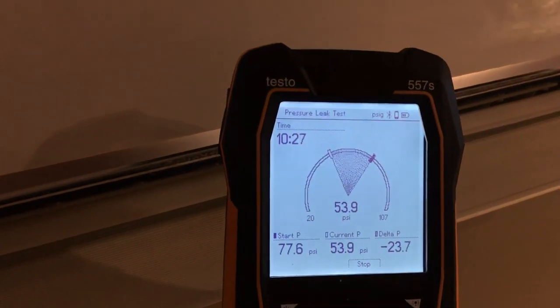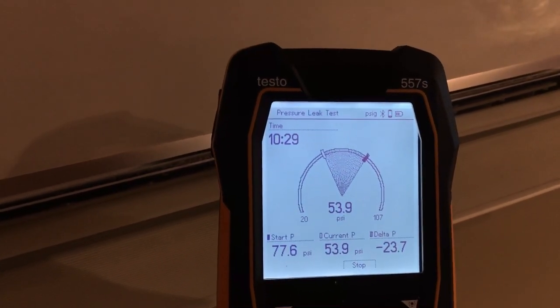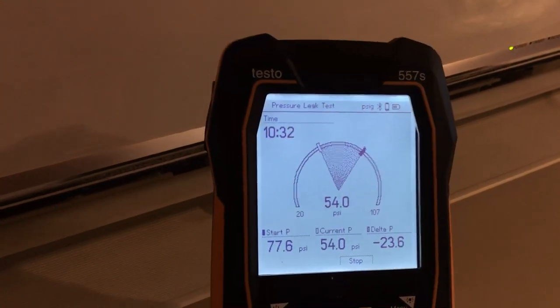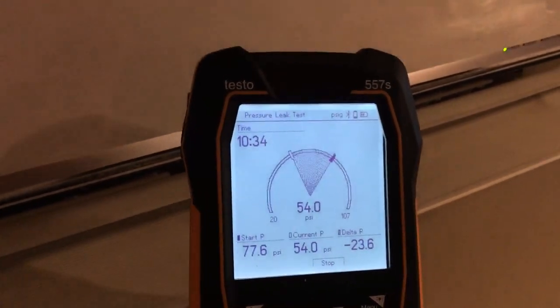So do not try to do pressure tests, standing duration pressure tests, with any kind of refrigerant. Dry nitrogen only. That's it.